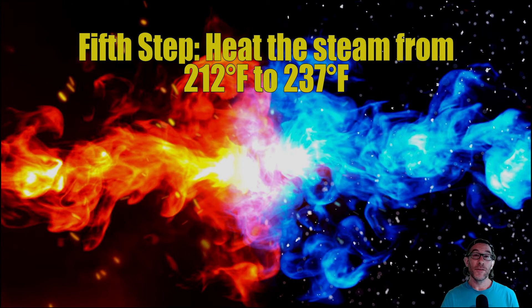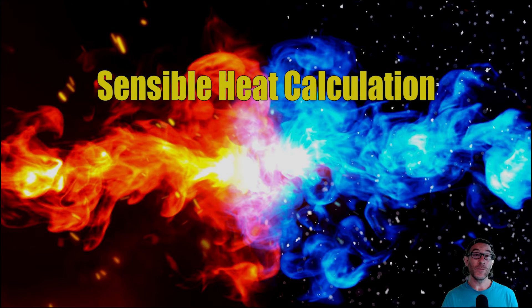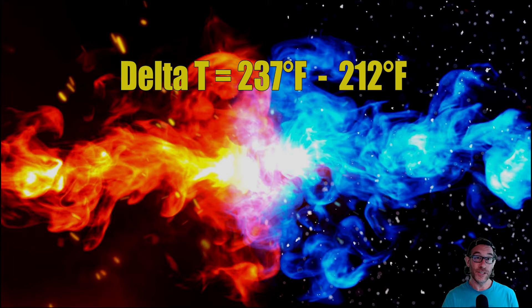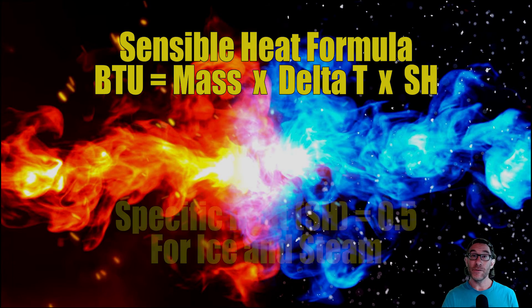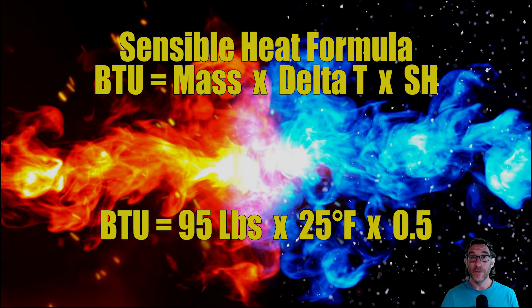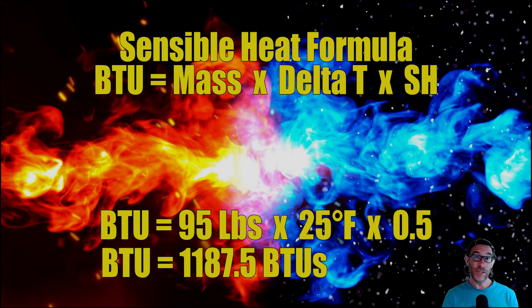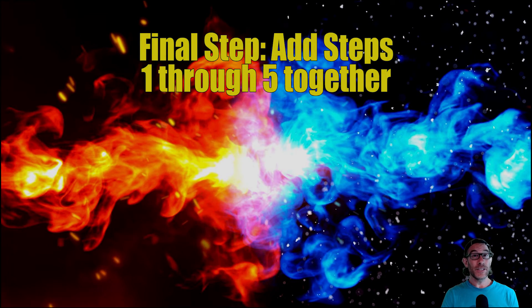We're getting close. Fifth step: let's take this steam, which is at 212 degrees Fahrenheit, and heat it all the way up to 237 degrees Fahrenheit. This is a sensible heat calculation. The delta T is 237 minus 212 degrees Fahrenheit, which gives 25 degrees Fahrenheit. The specific heat capacity of steam is 0.5. So BTUs equals 95 pounds times 25 degrees Fahrenheit times 0.5. To heat that steam up 25 degrees Fahrenheit, we'll consume 1,187.5 BTUs. Let's write that down.